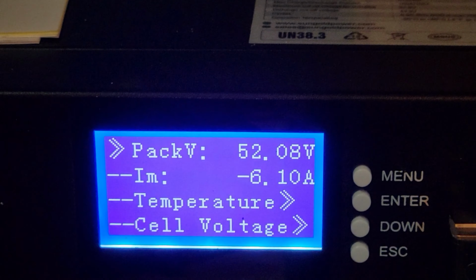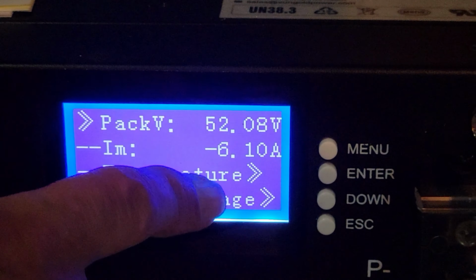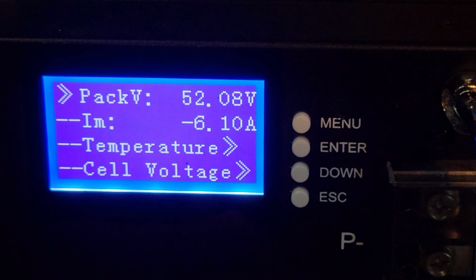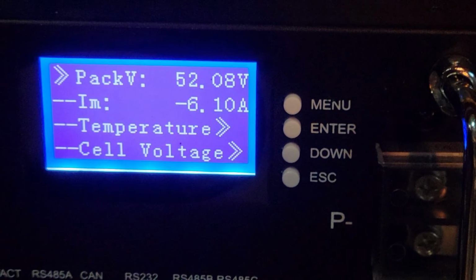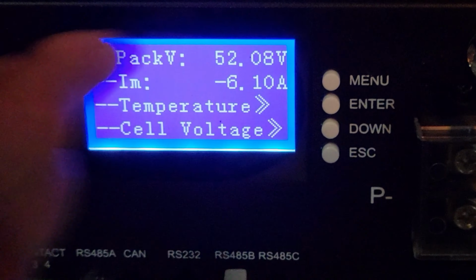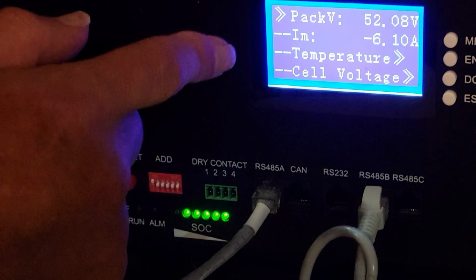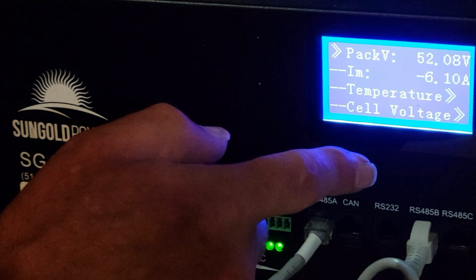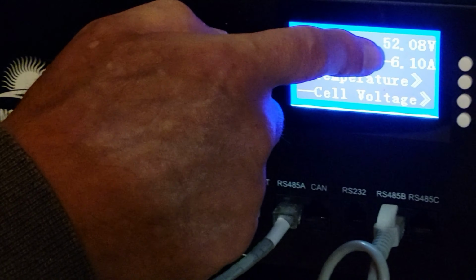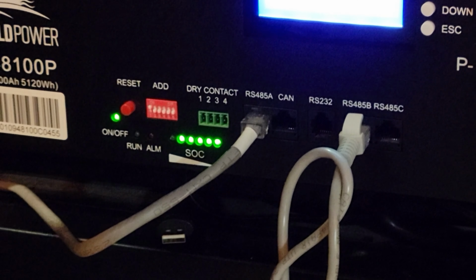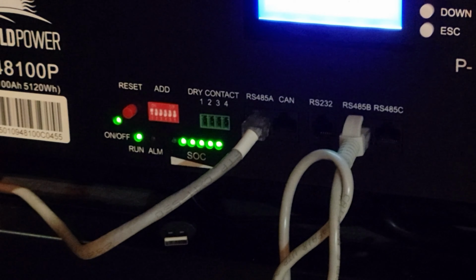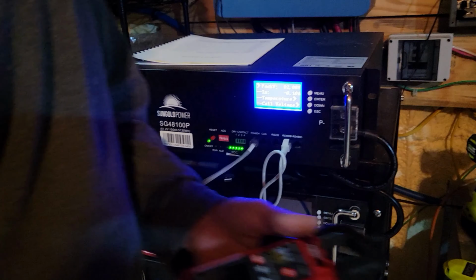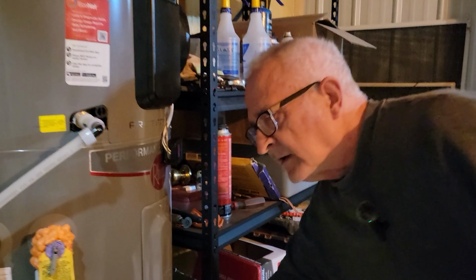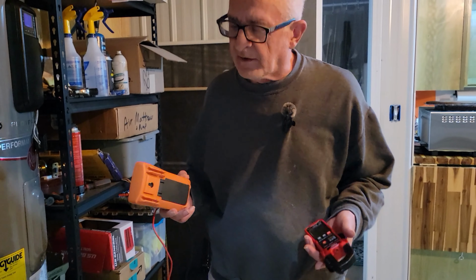If you're calibrating it, that'll be a positive number - it might be 60, it might be 20 amps - but it'll start dropping after this last LED stops flashing and your state of charge is at 100%. It'll go back to almost nothing when it gets done. You'd probably be okay just waiting till the LEDs stop flashing, but I like to let it go until the current stops dropping. It's nice to have the meters to keep an eye on everything, but they're not necessary.